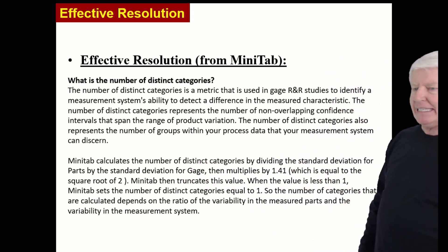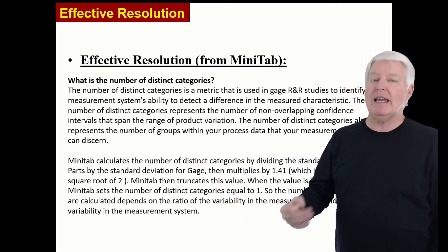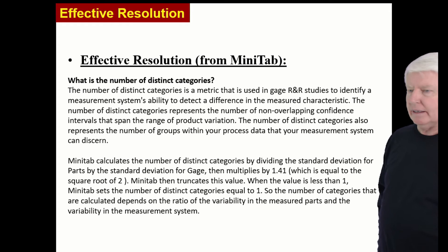But how does Minitab calculate it? Well, let's dig a little deeper into the woods here. Minitab calculates the number of distinct categories by dividing the standard deviation for the parts by the standard deviations of the gauge, or gauge R and R, or sigma of measurement, then multiplies that by 1.41, which is the square root of 2.